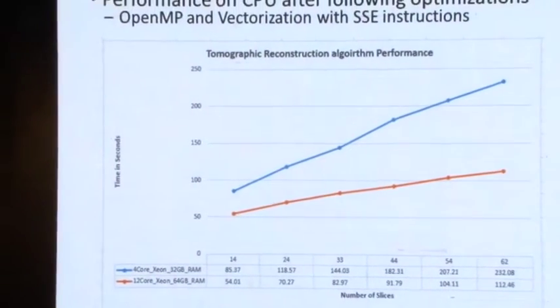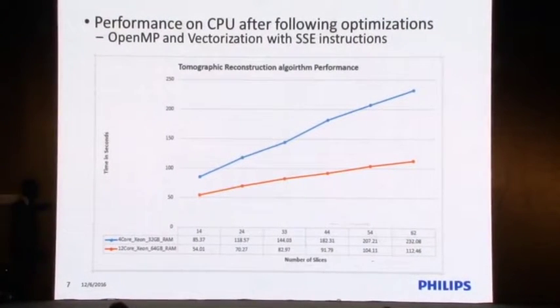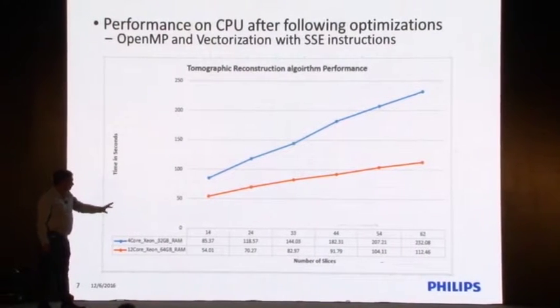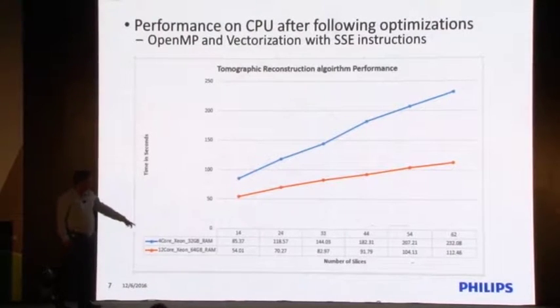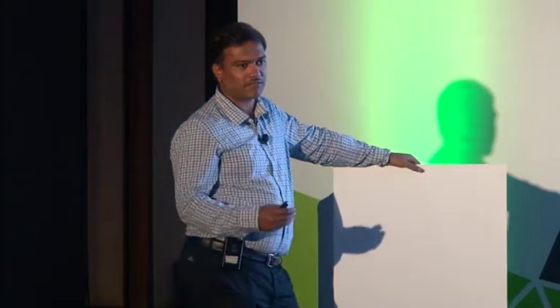While designing all of this, we developed a tomographic reconstruction algorithm — a statistical iterative, multi-stage algorithm. The fundamental problem is it takes a huge amount of time. After optimizing on CPU with OpenMP and SSE, a 4-core system still takes around 2.5 minutes and a 12-core CPU around 1.5 minutes. This was a big challenge — radiologists were happy with image quality and dose, but very unhappy with the long wait time.